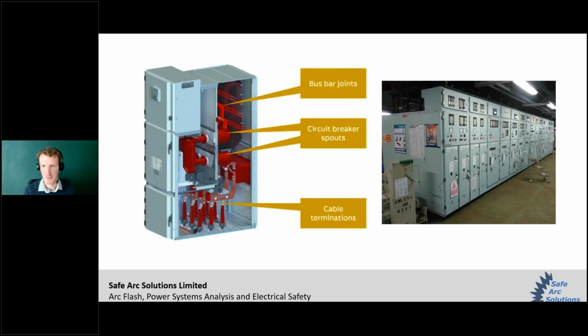When we think about medium voltage switchgear, this tends to be designed to try and keep those conducting parts and the live parts further back and away from the operator. So if someone's standing on the left-hand side of the equipment, a lot of the live equipment will be over further to the right. But nevertheless, even in this kind of equipment, you might have to get into the cable terminations to do some testing or inspection work, or you have the circuit breaker getting plugged into the spouts, which again is exposed copper work. So even in this type of equipment, there's still an arc flash potential there.